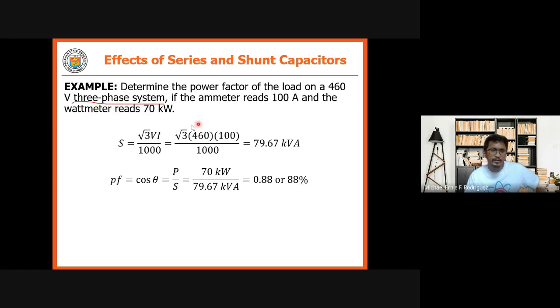So, square root of 3 times your voltage, which is 460 volts, times your ammeter reading 100 amperes, over 1,000. So that is 79.67 kVA.